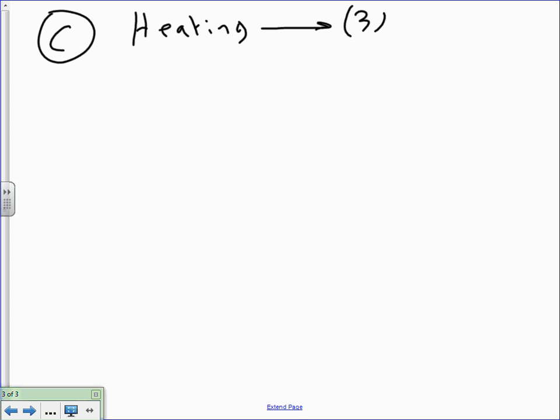Absolutely. Okay, C. I use C to designate heat. So I have my heating for the building, guys. We hired Jimmy, and he said, I'm going to use 3 heaters, and they're going to be drawing 115 kW, and they are 208 3-phase. Remember, we're a 208 3-phase system.